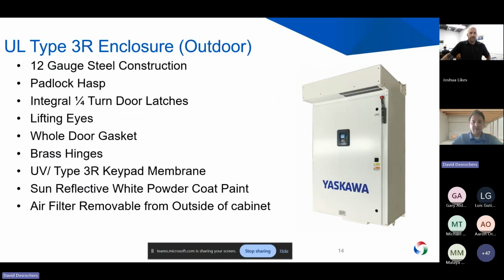Finally, the Type 3R enclosure is going to be the rain, wind, snow option. This is a full white powder coat enclosure, very heavy duty, with full intake and exhaust fans with filtering built into it. This is the one you're going to be using for rooftop units. Anywhere outdoors pretty much is your 3R enclosure. We don't have a NEMA 4X at this point, although I think you could do it custom, it just increases lead time, of course. But for standard options, this is your go-to for outdoor applications.